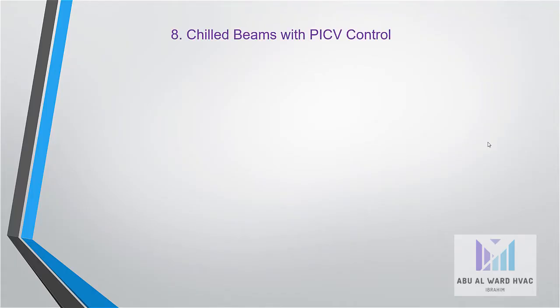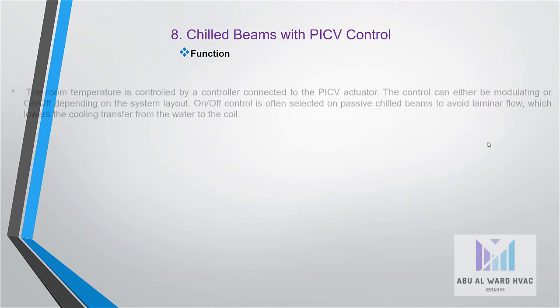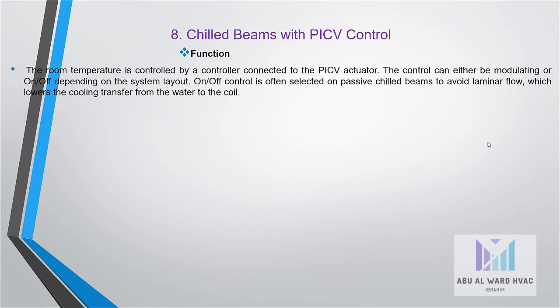Chilled beam with PICV control. Function: the room temperature is controlled by a controller connected to the PICV actuator. The control can either be modulating or on-off depending on the system layout. On-off control is often selected on passive chilled beams to avoid laminar flow, which lowers the cooling transfer from the water to the coil.